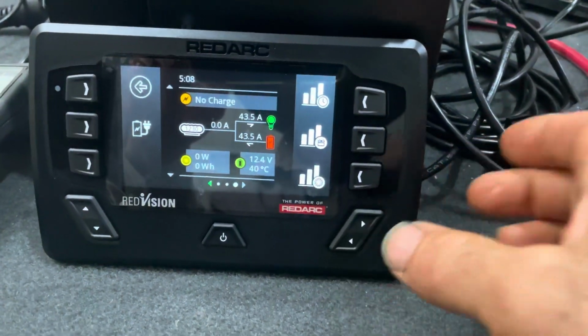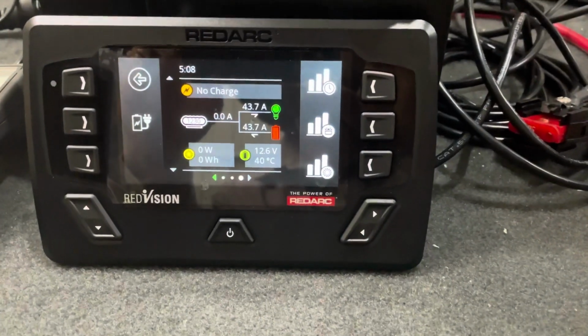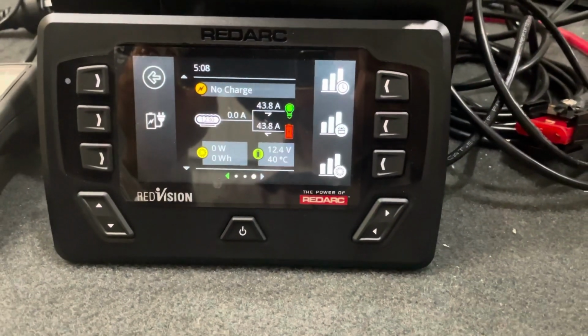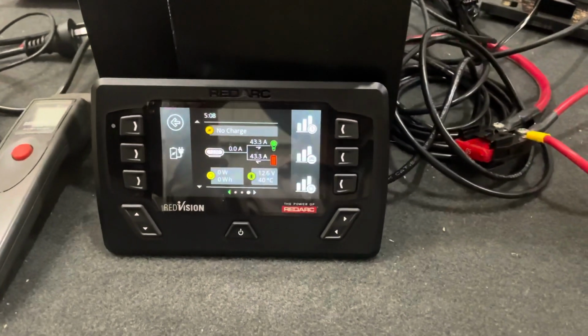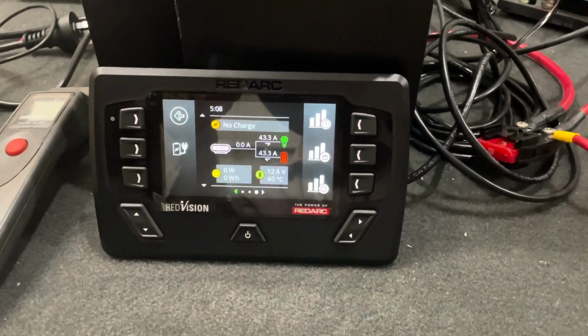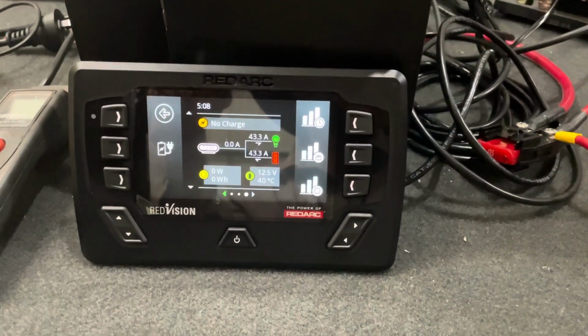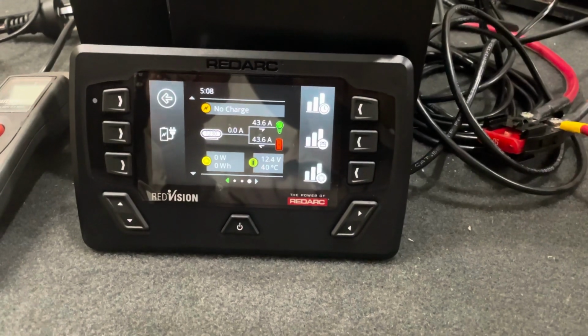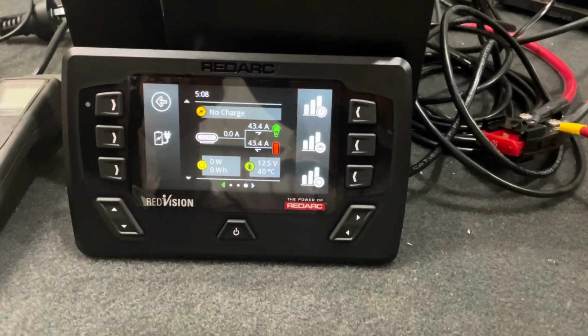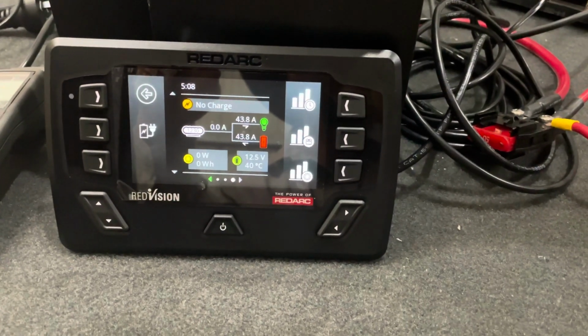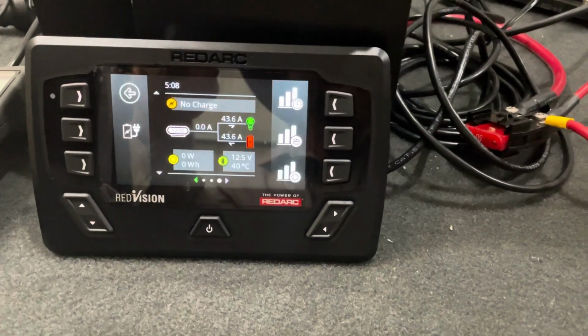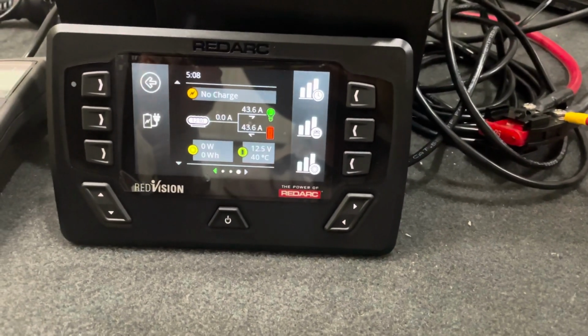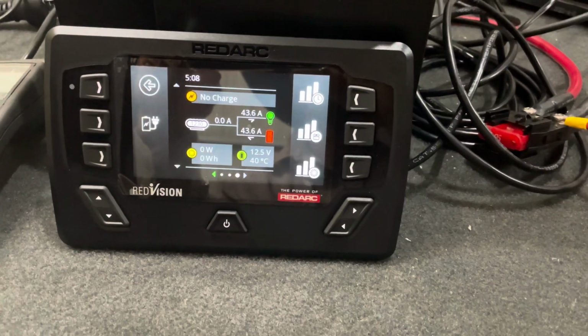Sitting at 12.4 volts, and now we're cranking at 40 degrees. I guess we'll run it for another hour and see if it makes it. By my calculations, it should run for a total time of 2 hours and 18 minutes to reach the 100 amp hour capacity at the average of 43.5 amps.